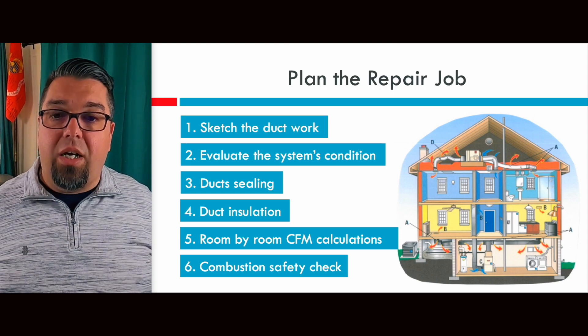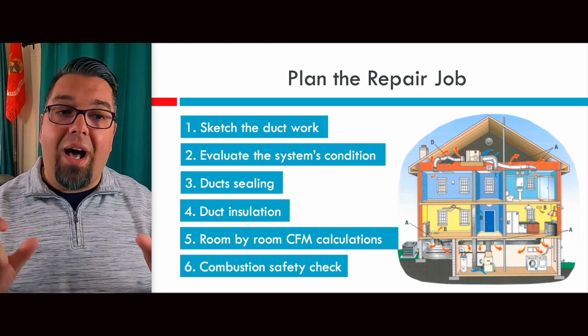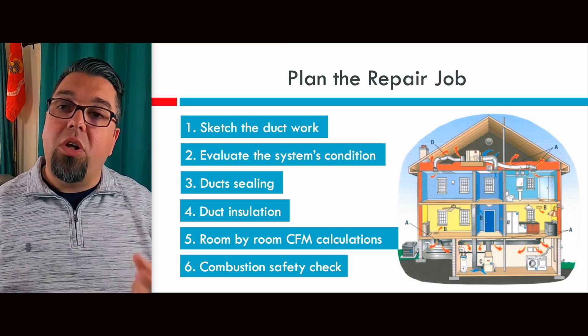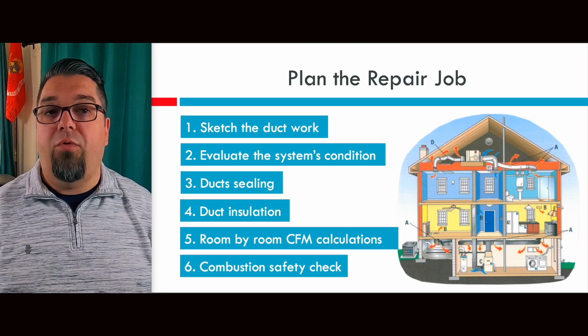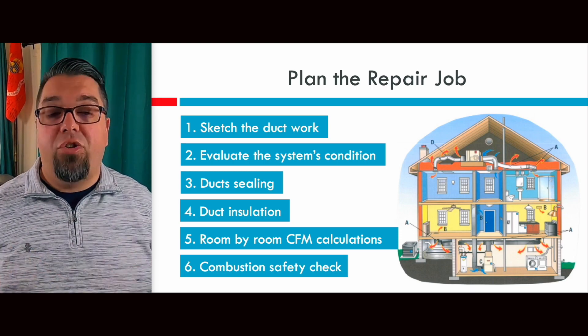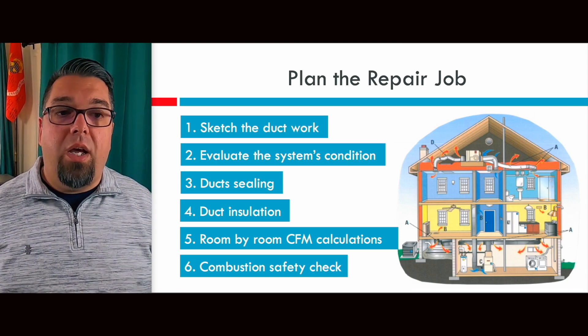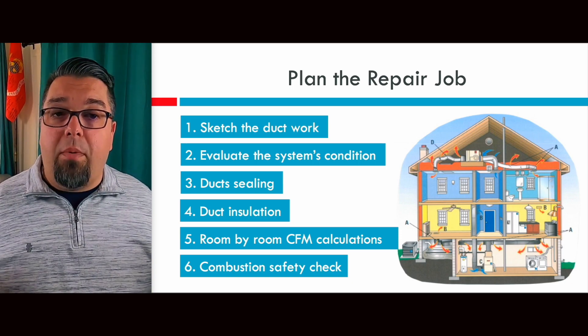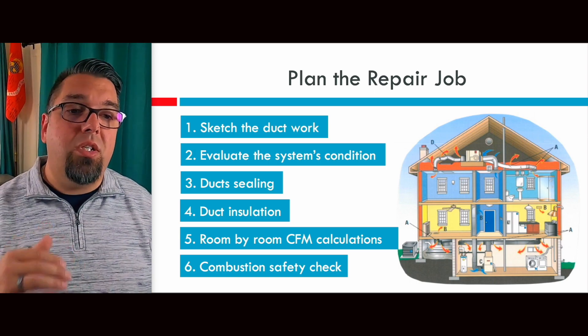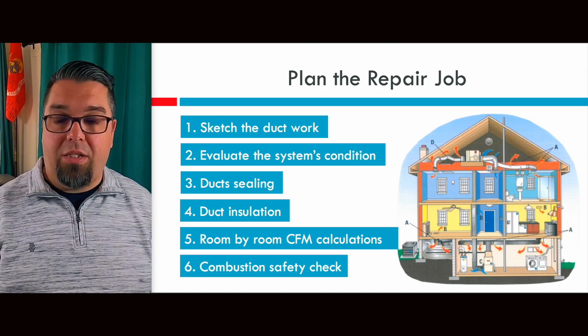When everything is said and done, you must do a combustion safety check because you're improving the house as a system by pulling air from the space. There are a lot of central returns out there from hallways and different areas, and you don't want to pull combustion products back from a naturally vented water heater in the basement or a fireplace and evenly distribute carbon monoxide around the house. If you do any duct system improvements or system replacements, you must do a combustion safety check if you have atmospheric appliances in the space.